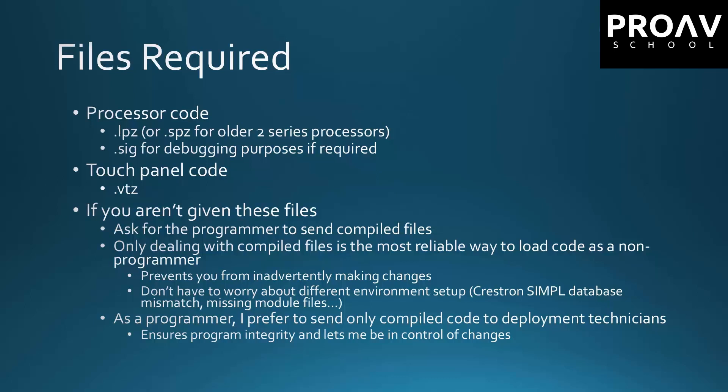That way, if changes need to be made, you can relay that information back to the programmer. They can make their changes in the master source code, send you the compiled changes, you load it — and as a programmer, they always have the latest version. I've seen things before where a programmer sends the uncompiled files, the guy on site makes a few little tweaks that are needed and it works, but that source code never gets back to the programmer. Six months down the road you go to make a change, but it's not based on the latest code. That's a problem we're going to try to avoid.